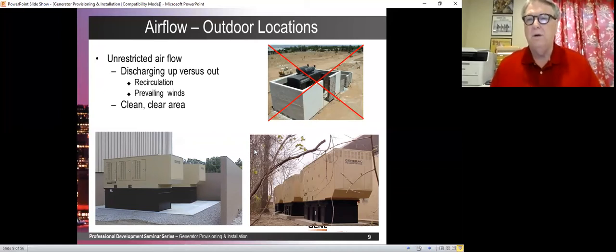Now we could have put a chain link fence there and that would have been fine. Make sure that we have a great deal of distance there so that it doesn't create a high pressure zone. But a better way of doing it is this upward directed exhaust here that you can see. In this case, the air comes in on actually 3 sides of the generator. On this side that you see, and on the opposite side, and then on the end, and then the air is exhausted vertically upward. This also means we can generally put the muffler or the silencer in the exhaust hood and exhaust upward. If you have multiple generators, one of the nice things about those is that you have a lot of flexibility in terms of where you're going to mount that generator.